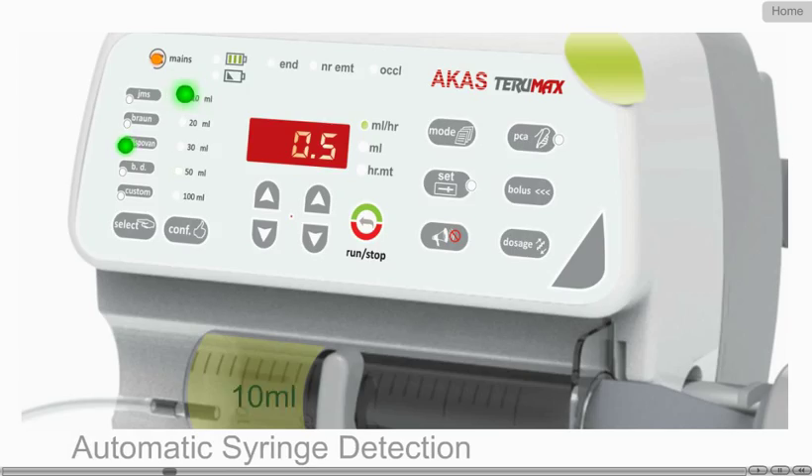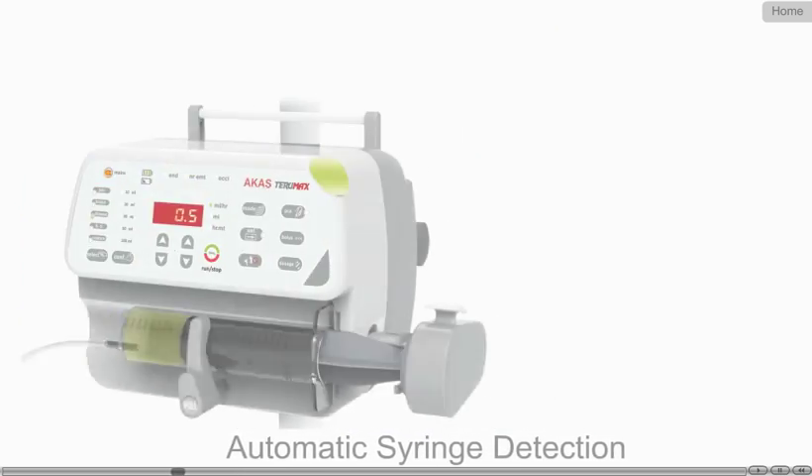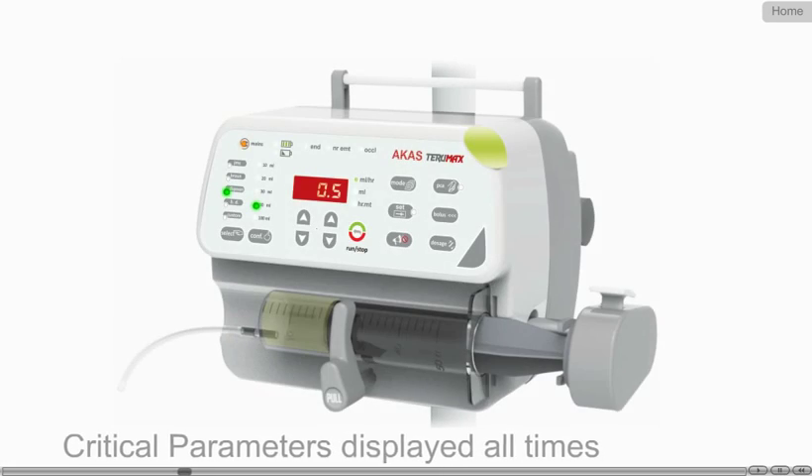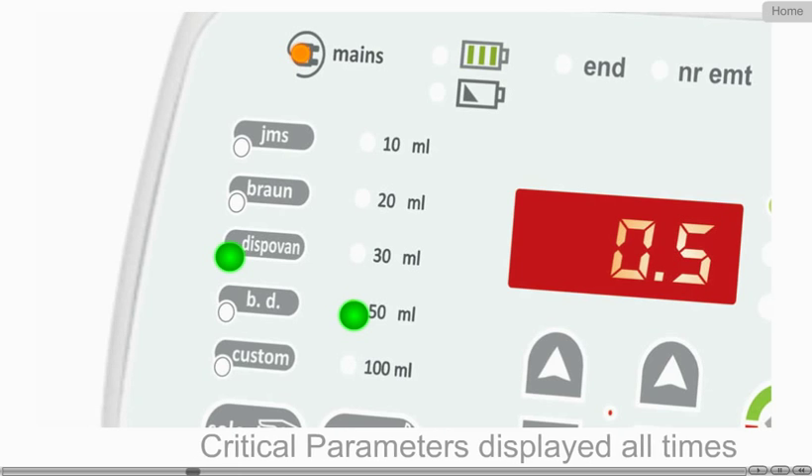Our AKAS syringe pumps can automatically detect the size of the syringe used, thereby avoiding manual wrong selection.